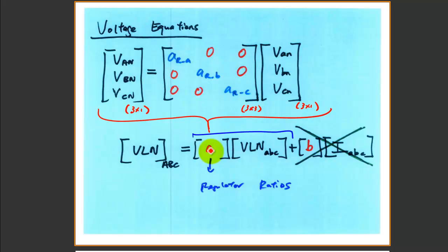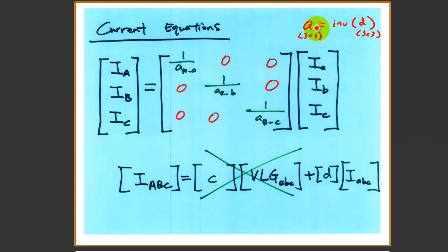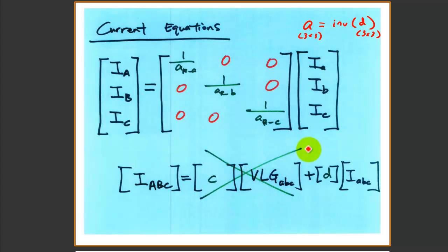In terms of equation, it's the same thing. The capital A is actually the inverse of D. Since previously it was only the diagonal, you can invert it so that you have capital A and small a. We don't have a C term because we don't care about the shunt admittance information from the transformer — the amount of shunt is so small. So we only compute the D part of the matrix multiplied by the right-hand side current — small abc, which is the receiving side — and capital ABC is the sending side. That is pretty straightforward for Y-connected three-phase regulator configuration.